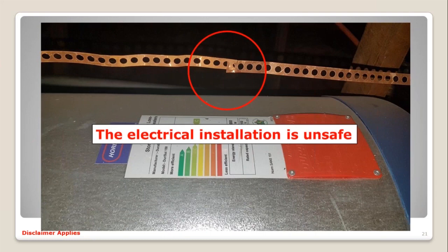You can see the installation, the replacement was done where the bonding strap was cut and just squished together to make continuity. But the issue here is the surface contact between the two is so minimal that there's no use in using that strip again. Next slide.